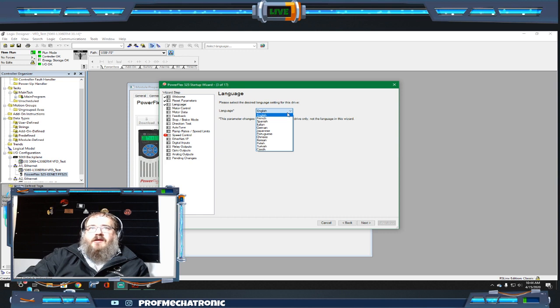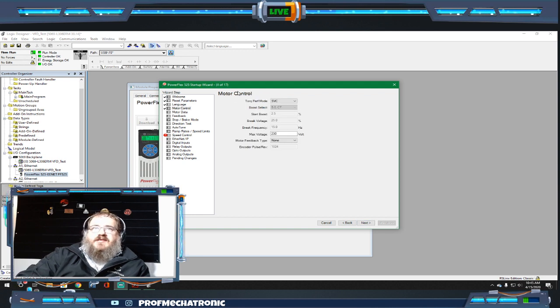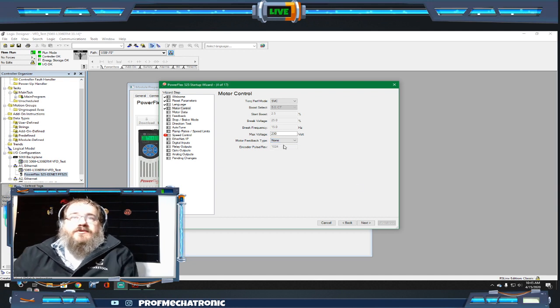Do you want this in English or French or Turkish? You can actually set up your language from here. You can go to the next and actually set up your motor control. What kind of torque motor are you going to use? Voltage per hertz, SVC, economizer. What are you going to use to actually do your torque performance mode? What kind of boost? What's the maximum voltage? Is there motor feedback? Yes or no, right? Are we using an encoder? Is it a single channel? Is it pulse train? What are we using?